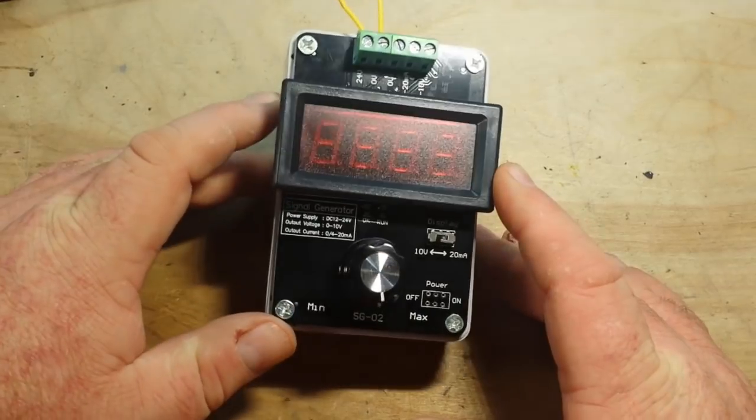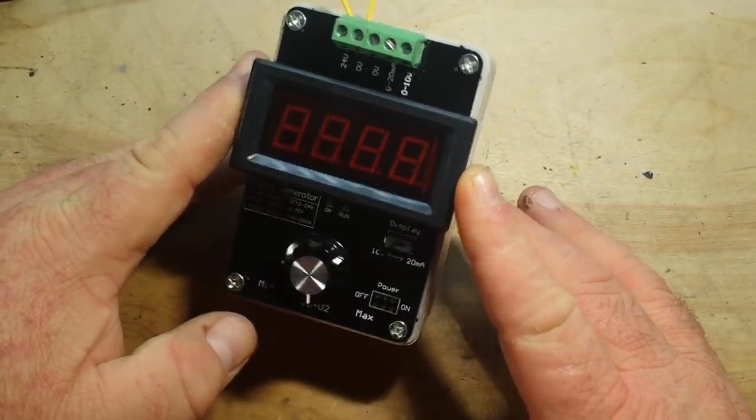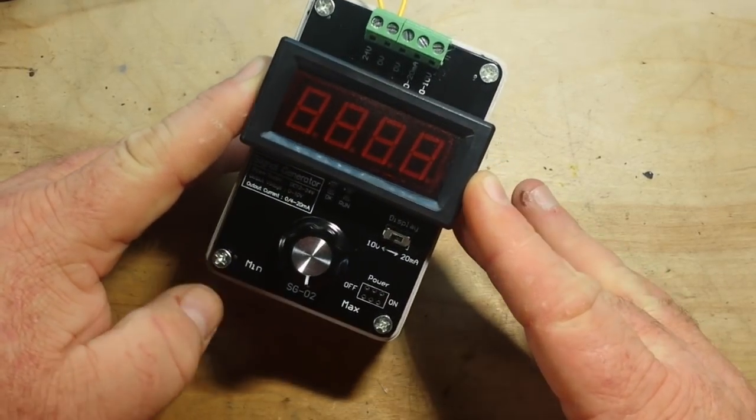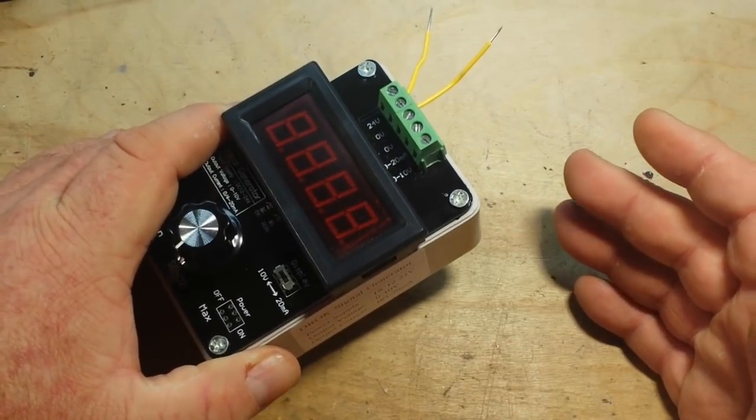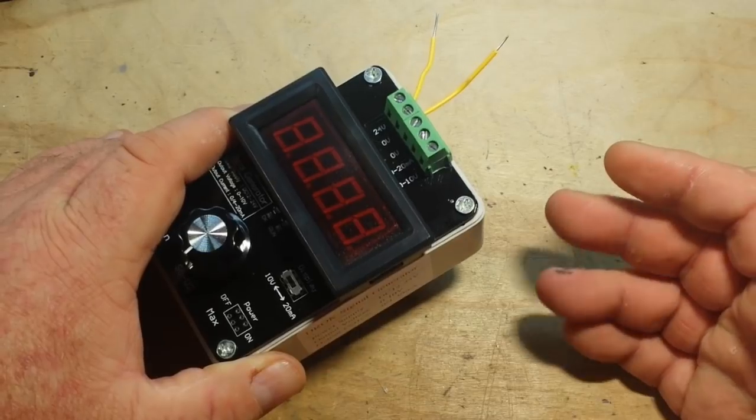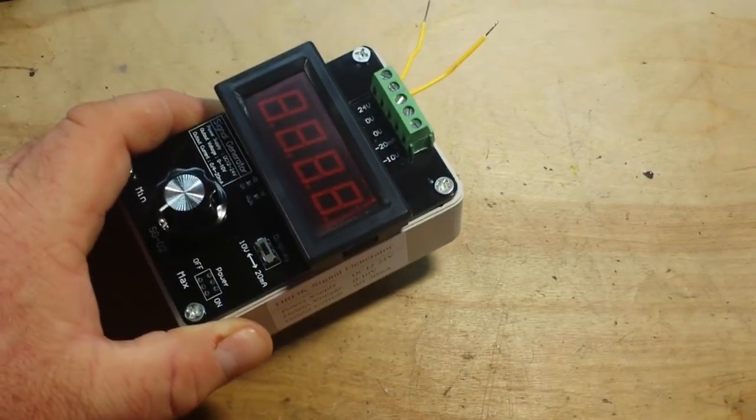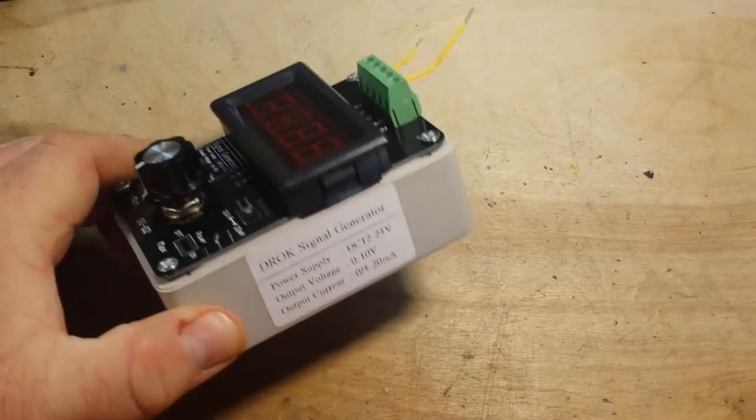It needs 12 to 24 volts in. It outputs 0 to 10 volts or 4 to 20 milliamps out. These kinds of devices are used in testing different things such as programmable logic circuits, valves and sensors. They're also known as an analog simulator. Fluke makes them for three or four hundred dollars, but this is 20 bucks or so from Amazon. So I thought we'd give it a little play.